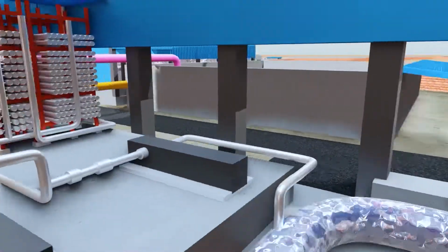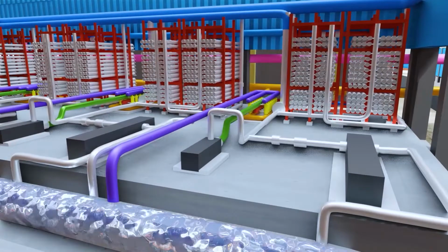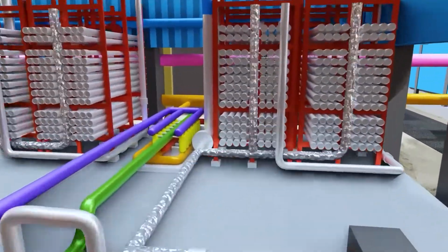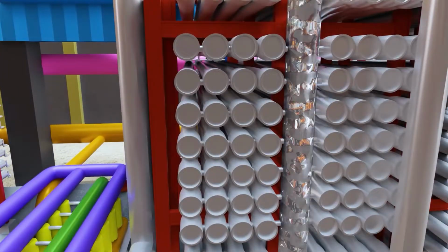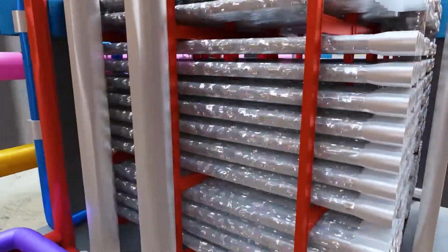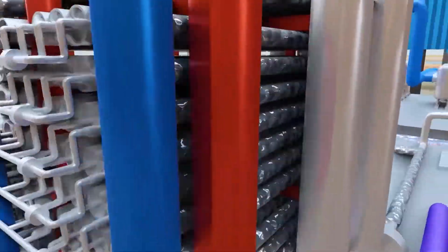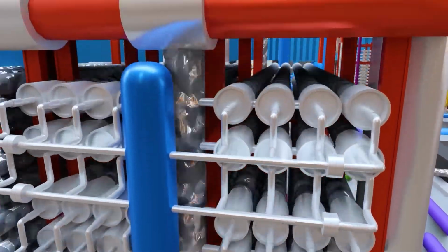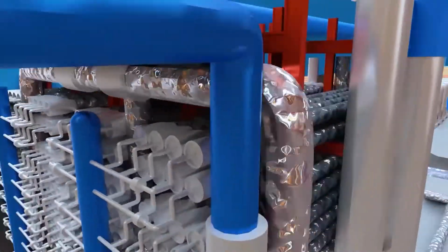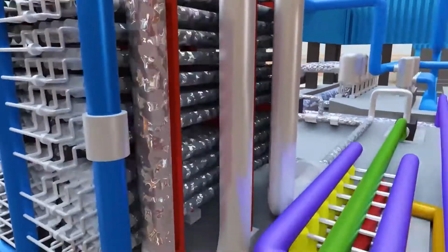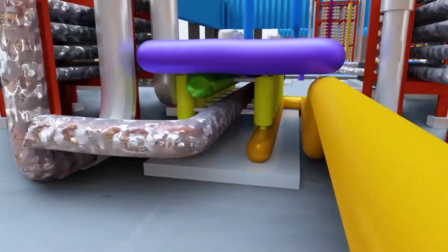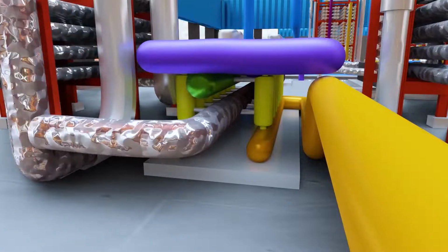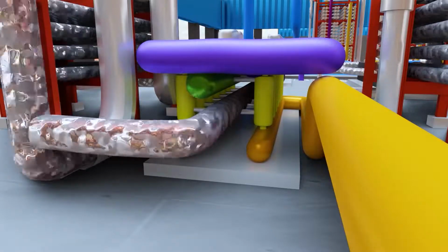After filtration, water will move with high pressure into the inlet of RO skid with the help of a high pressure pump. The reverse osmosis process will occur in the RO skid. The reject water will be released out of the RO skid with the high pressure. Such high pressure can be utilized to recover the energy of the system. To fulfill that purpose, the reject water can be used to recover the energy and enhance the pressure of service water with the help of an energy recovery device.